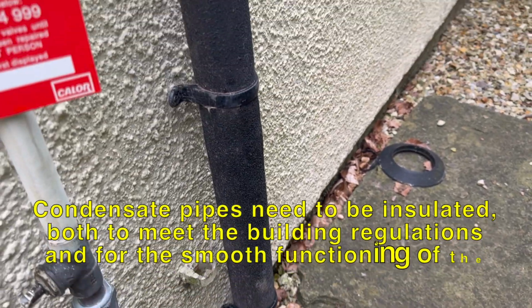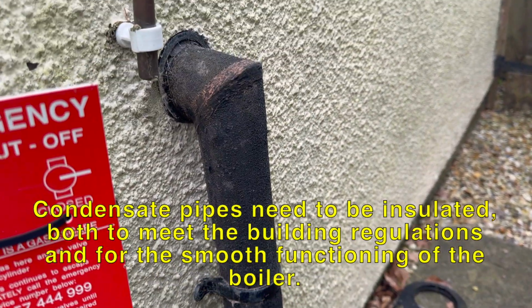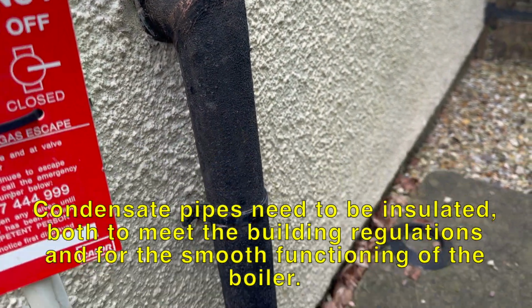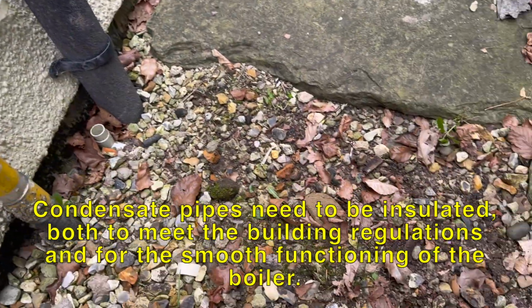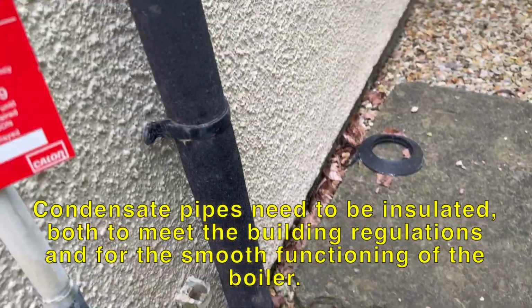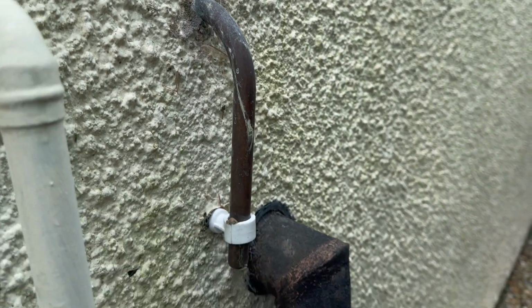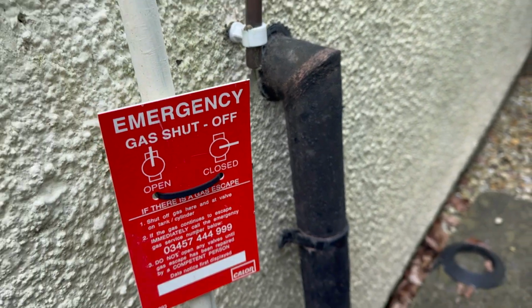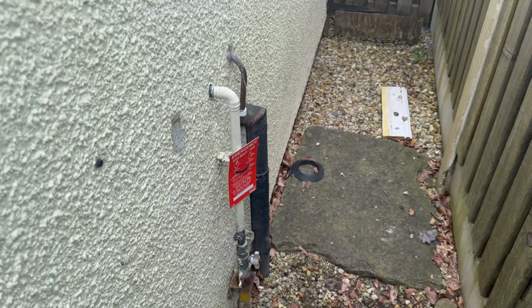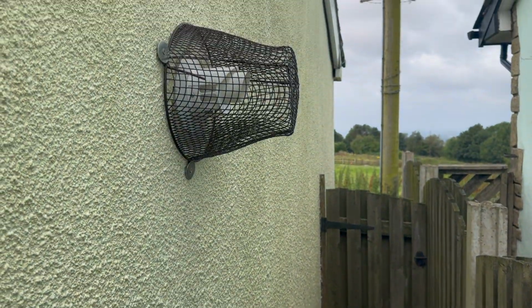So we have the condensate pipe. It's got Condensate Pro on it, so it's insulated and it goes to a soakaway, which is good. And then finally the blow-off terminates correctly. So everything seems to be correct outside here.